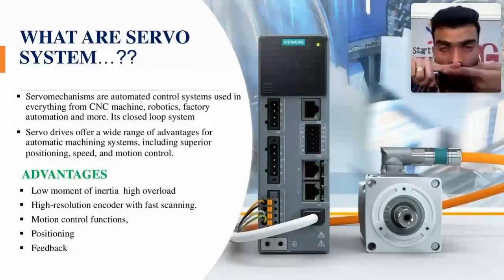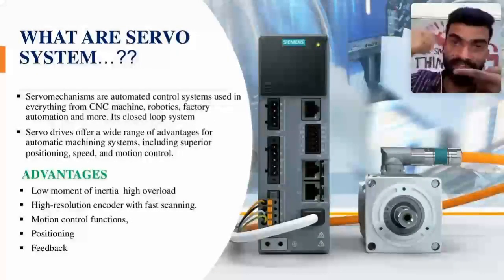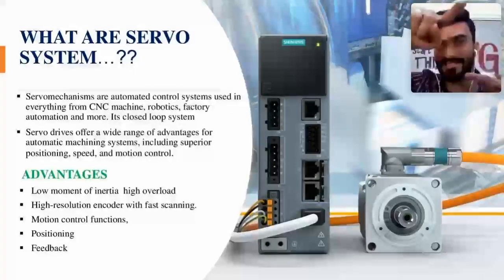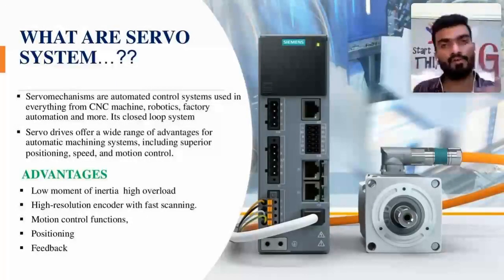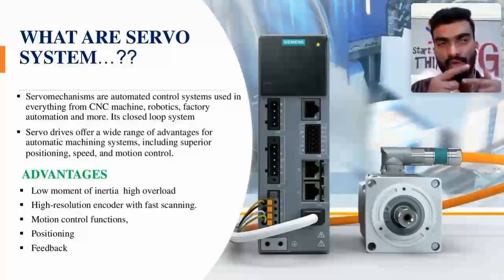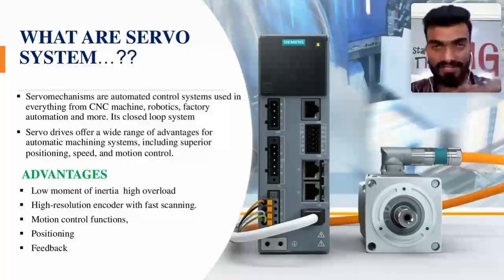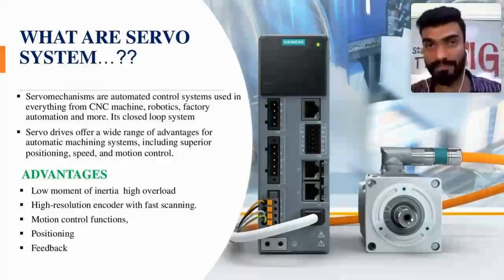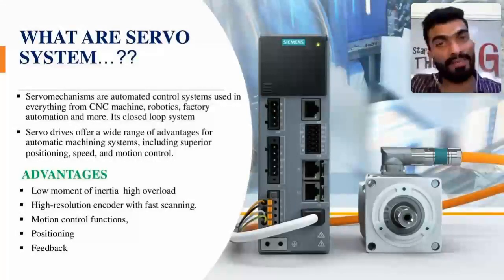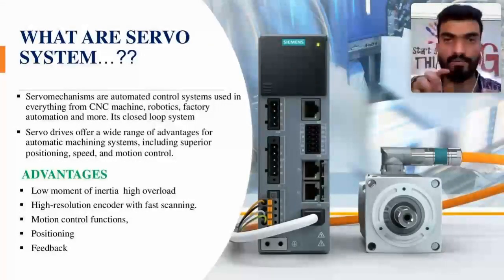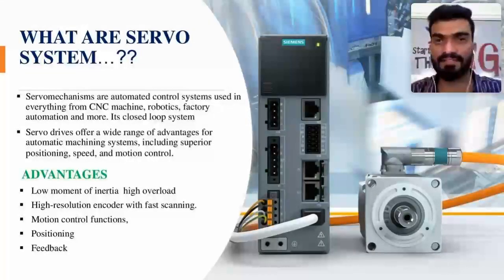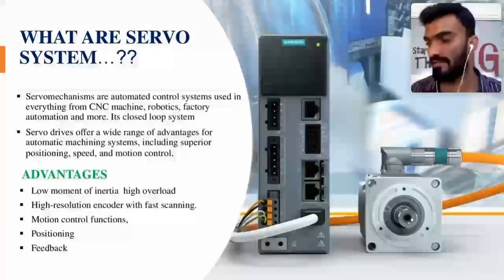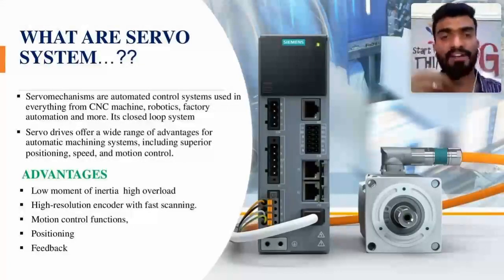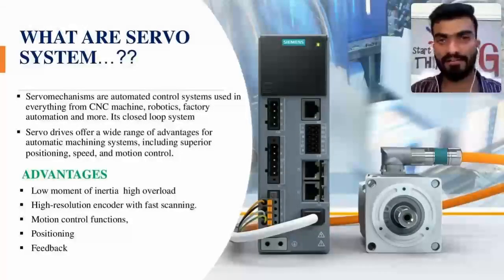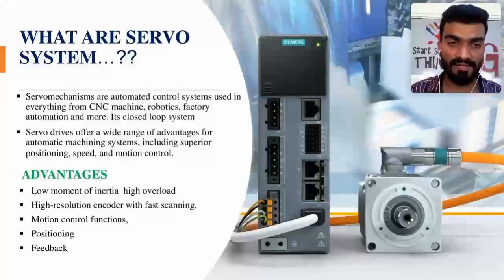However it is rotated, my encoder will give time-to-time feedback to my drive, to my PLC, and to my HMI. So what I want to tell here is, whatever direction, whatever rotation the motor is taking, time to time we'll be getting feedback through this encoder. So the feedback system is a benefit in this servo, whereas in an induction motor the feedback system is very low, I can say. But here we have integrated encoders, different types of encoders, absolute encoders and incremental encoders, where we can get more accurate data.